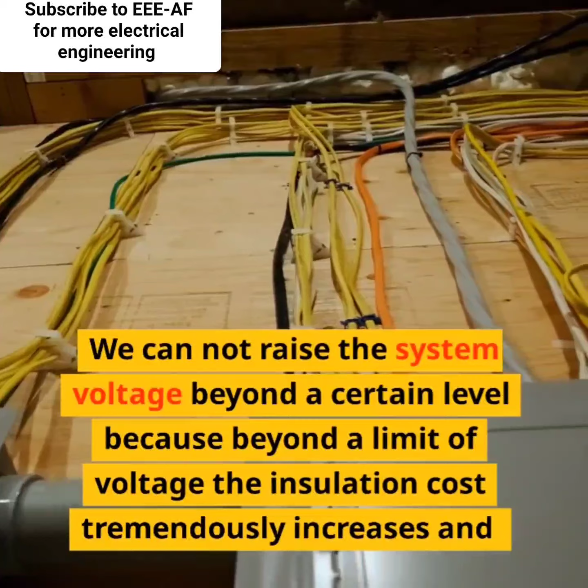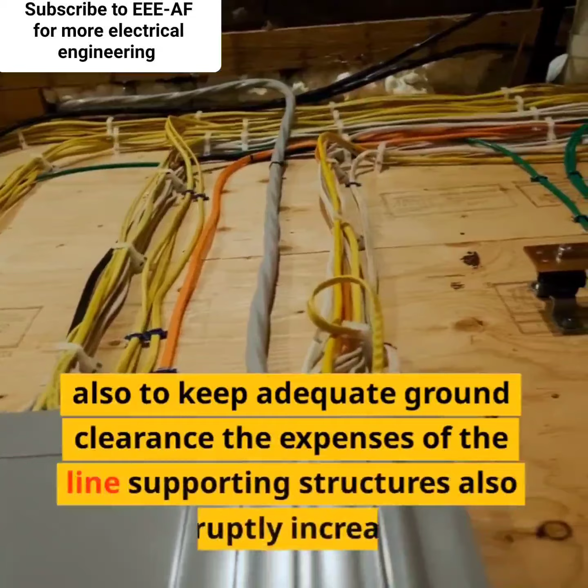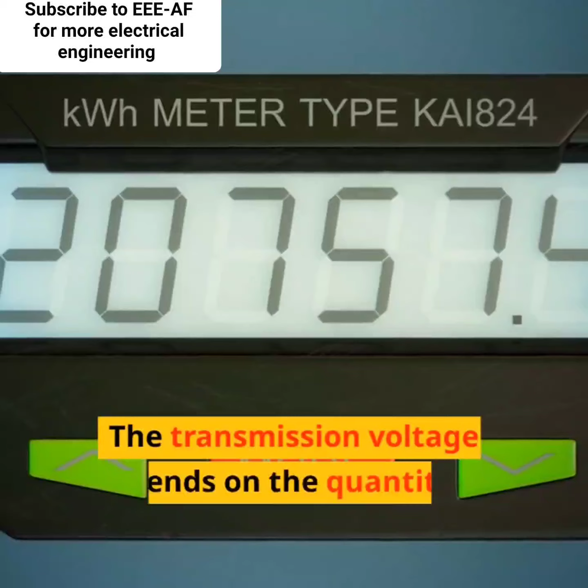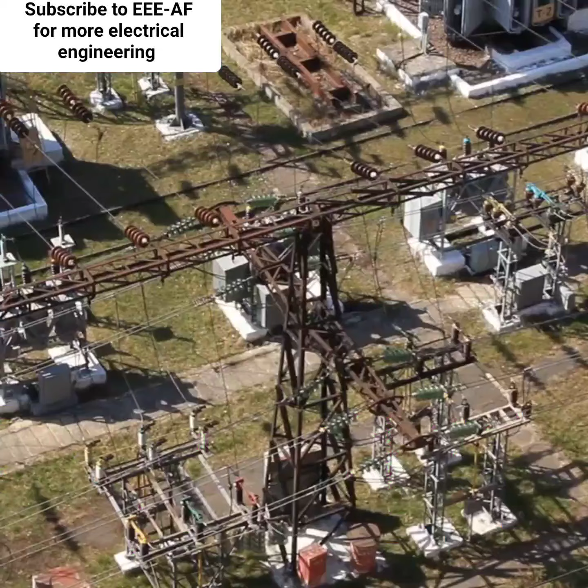We cannot raise the system voltage beyond a certain level, because beyond a limit the insulation cost increases tremendously, and to keep adequate ground clearance the expenses of the line supporting structures also abruptly increase. The transmission voltage depends on the quantity of power to be transmitted. Surge impedance loading is another parameter which determines the voltage level of the system for transmitting an amount of energy.